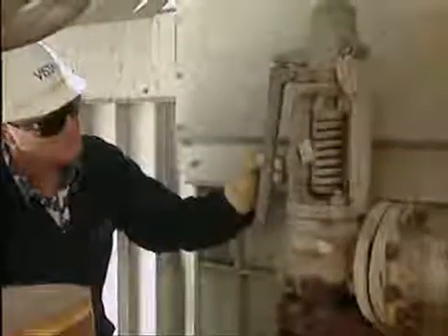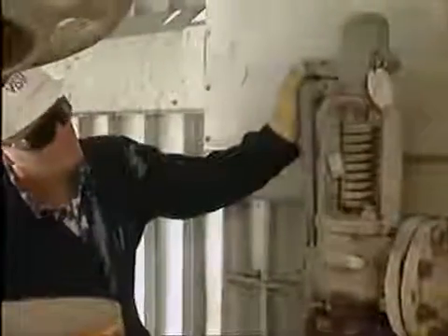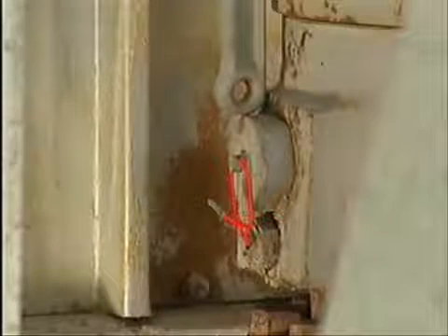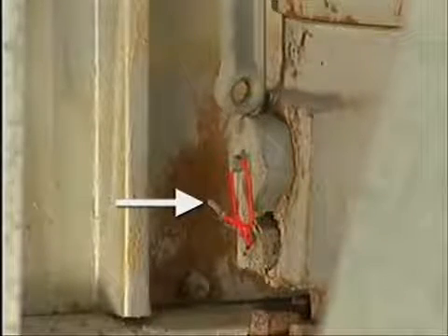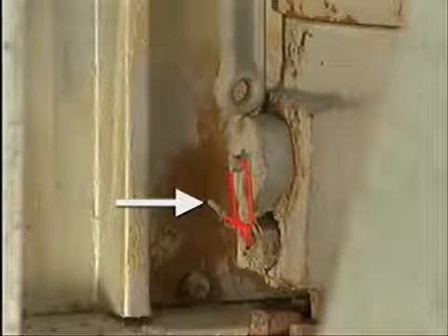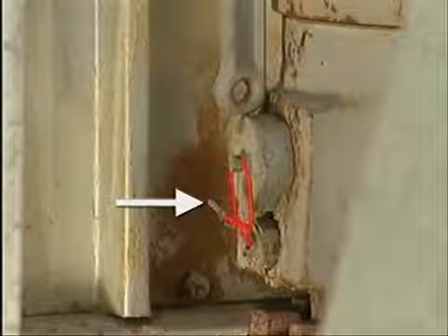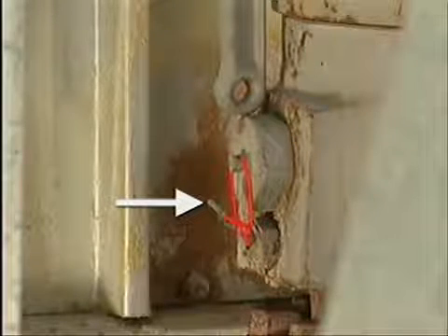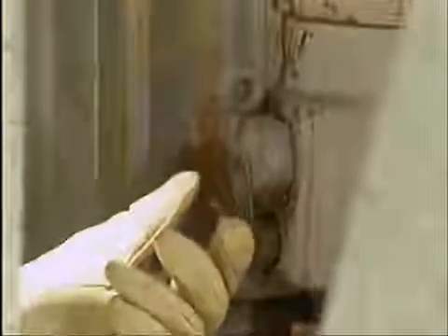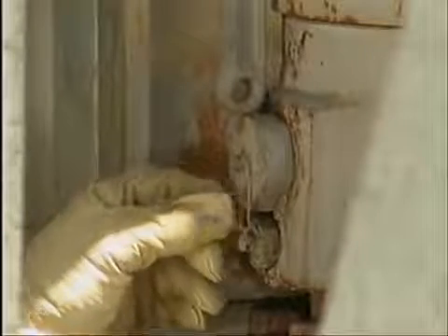For this two-ring huddling chamber safety valve, first check the lock wire on the adjusting ring pins. The lock wire is fastened in place with a metal clip as the final step in the valve reassembly procedure. So the presence of the metal clip is a sign that the adjusting rings should still be properly set for operation. If the metal clip is missing, or if the lock wire has been tampered with, the valve set points may not be correct. Then you must have the valve taken to the shop to check the adjusting ring positions, and if necessary, reset them.